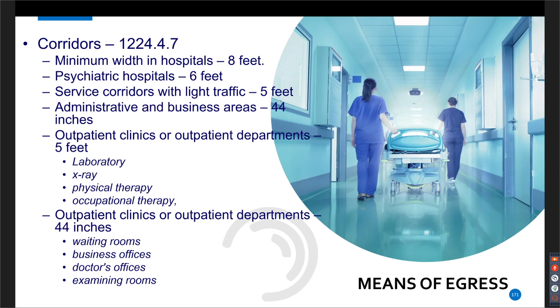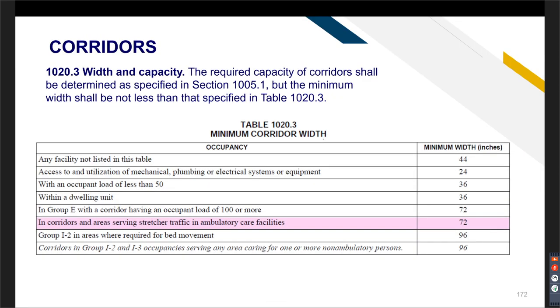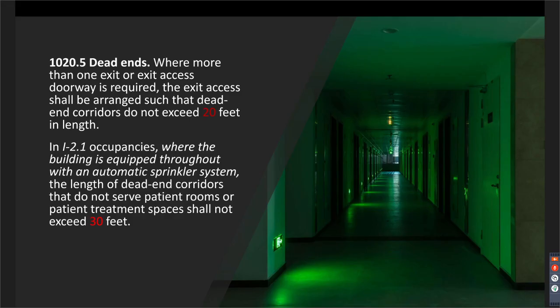And then outpatient clinics or outpatient departments could go to 44 inches in areas like the waiting rooms, the business offices, doctor's offices, and examining rooms. So this particular section of the code is disconnected from the chapter 10 requirements. The point here is that even though this section says outpatient clinics can have 5-foot corridors, a new amendment to this section says, by the way, go see section 1020 for corridor widths. And 1020.3 requires 6-foot corridors serving stretcher traffic in ambulatory care facilities. So be aware of this disconnect, and the provisions of chapter 10 still apply. Yes. And that's still in work for cleanup, because there's a footnote that was added to chapter 10 that leads you back to 1224. So that's still a little bit of cleanup.